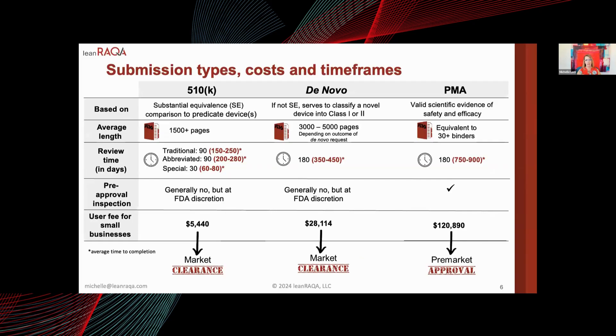In the US, a successful 510k is built on substantial equivalence — a comparison to a predicate or already legally marketed device with an existing regulation and product code. Substantially equivalent doesn't mean identical; it means in terms of intended use and technology, it's similar enough that it's not raising new questions of safety and efficacy. If you can't make a substantially equivalent argument and don't fall into an existing regulation, you are new and novel but moderate risk, so you go through the de novo process. In terms of length, you're ranging from 500 to 1,500 pages for a 510k and around 4,000 pages for a de novo.